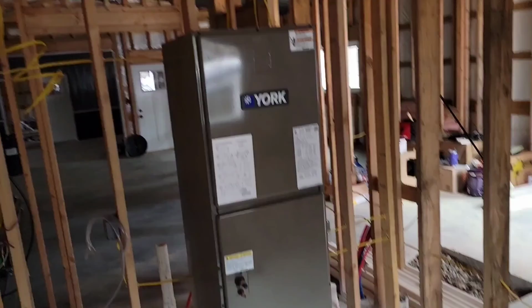Finishing up a job this week. I'm going to show you the rough in though. We've got the ductwork installed here. We're about to install this air handler. And this section, this building is getting a 3-ton split heat pump, HMH7, so modulating heat pump. I'm going to show you the ductwork, show you how far we've gotten here, what we did, and then we're going to go over and take a look at the other section and look at the mini split install.